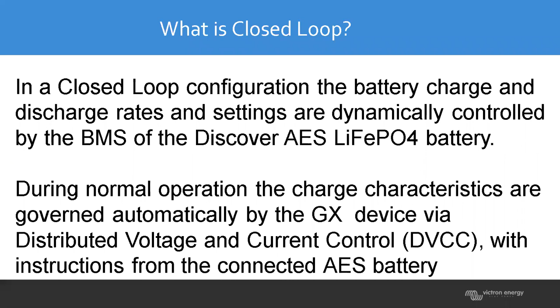Okay, what is closed loop? In a closed loop configuration, the battery charge and discharge rates and settings are dynamically controlled by the BMS of the Discover AES battery. During normal operation, the charge characteristics are governed automatically by the GX device via the distributed voltage and current control, or DVCC, with instructions from the connected AES battery. Okay, we have closed loop.